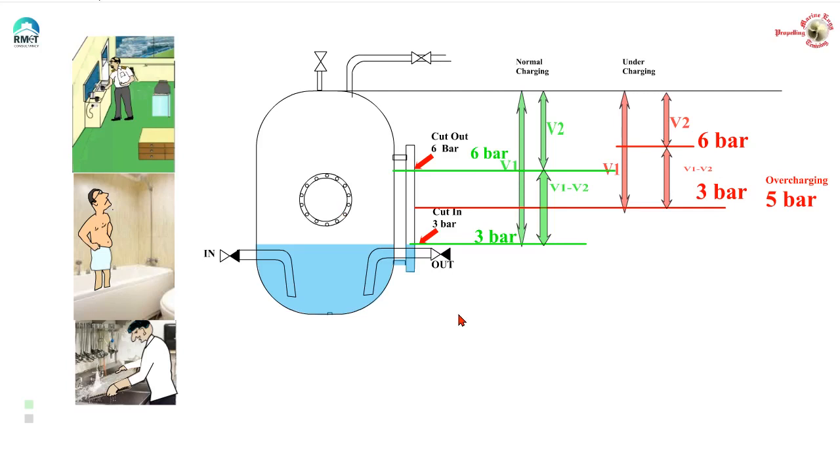Now let's tackle question number one: What is the correct method of charging the hydrophore? We already made a beginning by saying that the whole idea is to ensure that water reaches everywhere. We want to ensure that water reaches the bridge at the minimum pressure available on the hydrophore, which we can also call it as the cut-in pressure. Now in this example, I am taking a cut-in pressure of three bar. Now how do I determine this cut-in pressure? You can determine the cut-in pressure by keeping two or three taps open in the galley and the accommodation and checking up with the bridge if water is still available in that mini pantry.